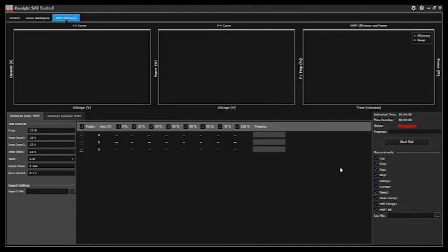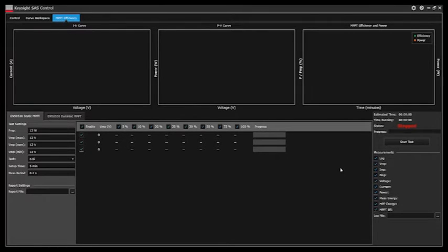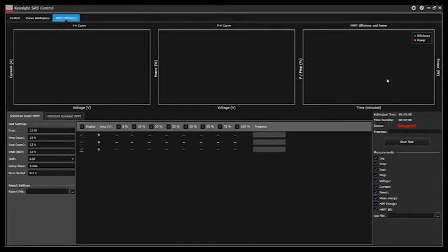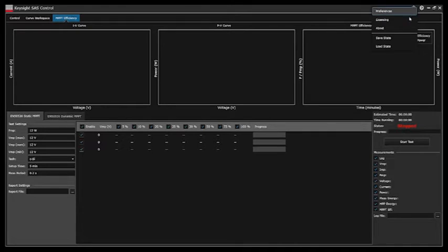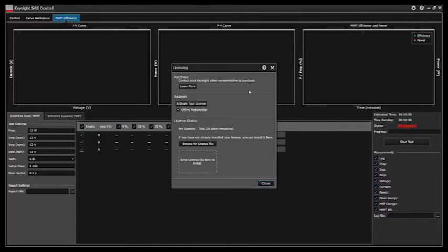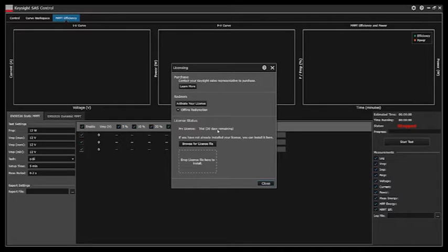The EN50530 MPPT efficiency test is a licensable feature in the SAS control software. Each version of the SAS control software comes with a 30-day free trial of the pro feature. You can access this by hitting the settings icon and going into the licensing tab. You'll see that we already have a 30-day trial license enabled.